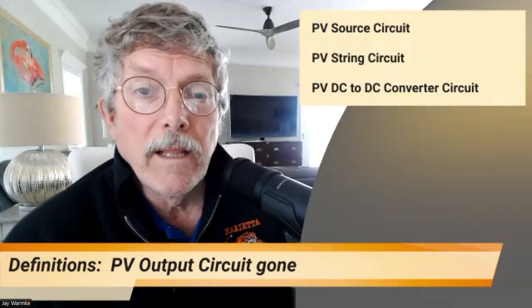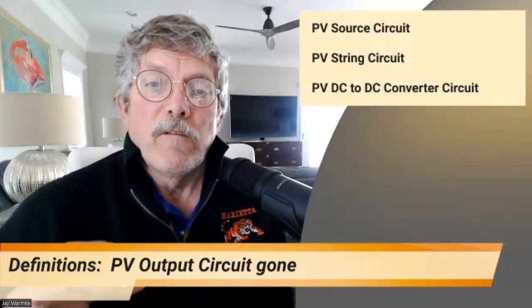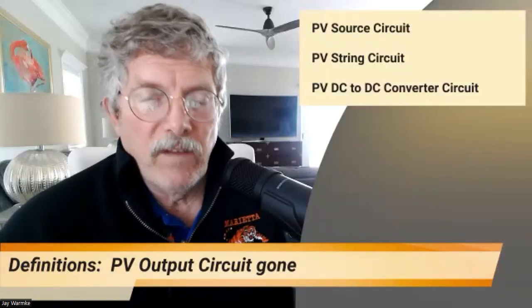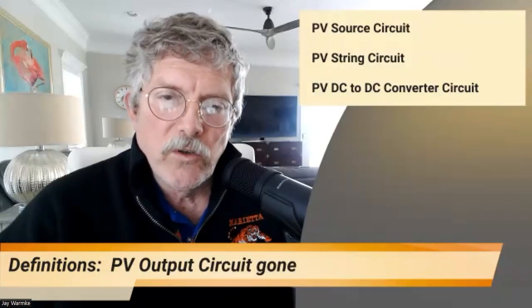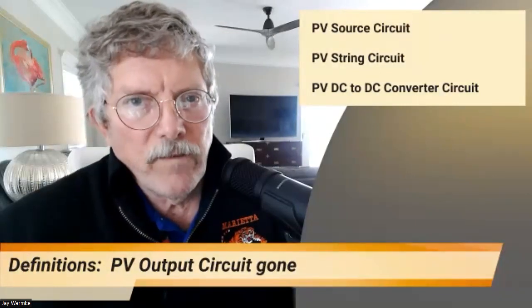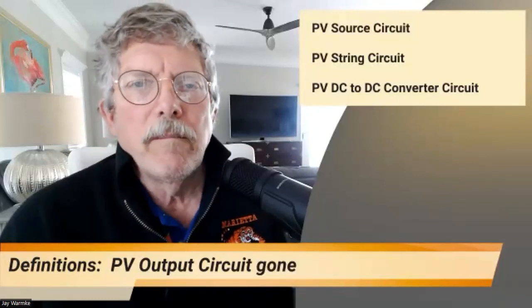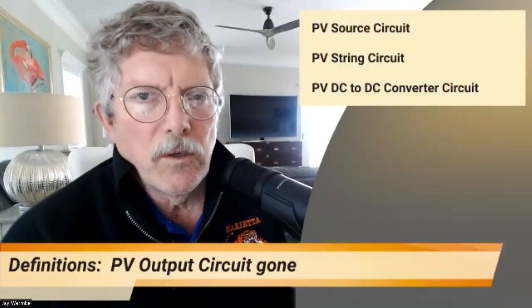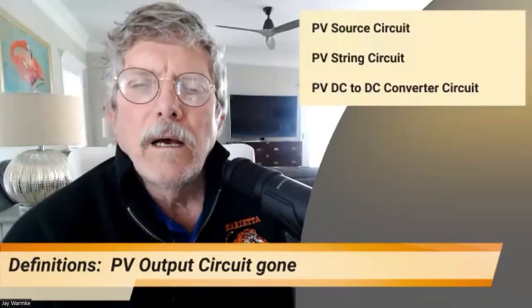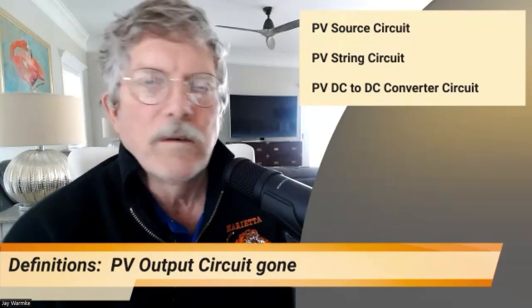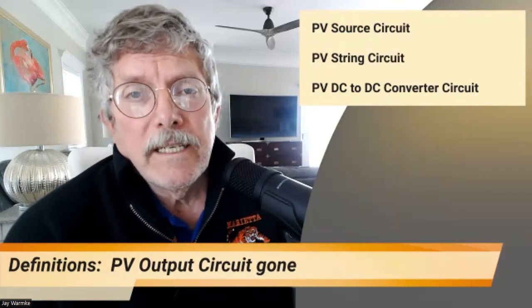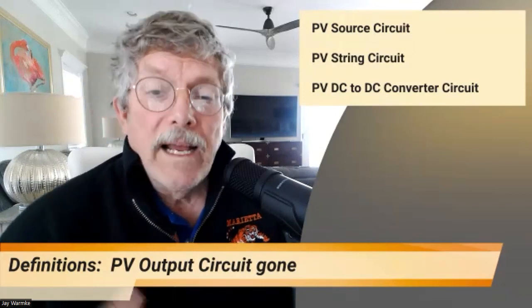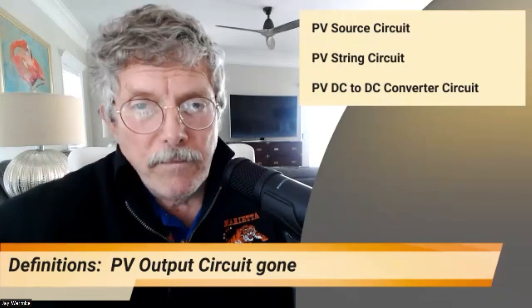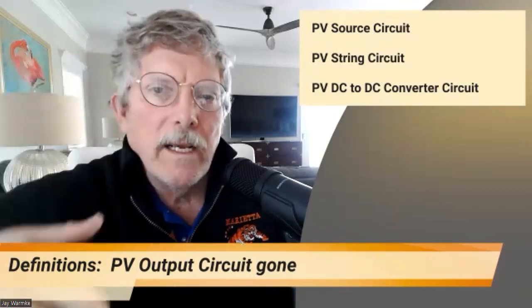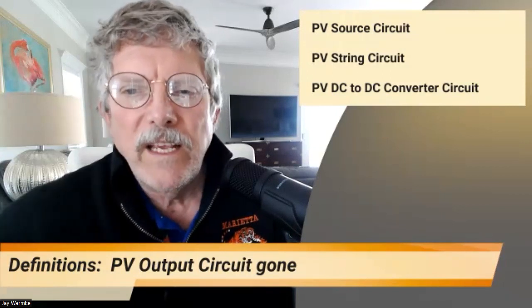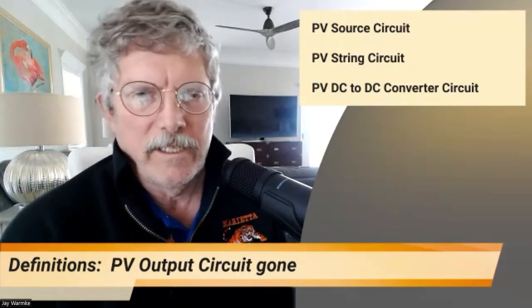If you're combining in parallel in a combiner box, from that point forward, it would no longer be a PV string circuit. But if you're going from a string to an inverter, which we oftentimes do, and you might have multiple strings coming from the array to an inverter because of multiple maximum power point tracking, those would be PV source or PV string circuits. But if it's connected in parallel, it would be a PV source circuit. But if it is connected to a power optimizer, for example, from the optimizer to the DC disconnect, that would be referred to as a PV DC to DC converter circuit.